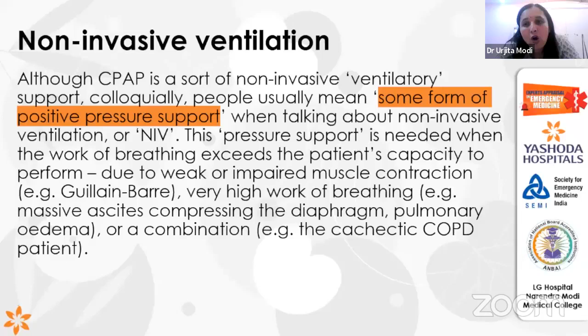And the machine has a trigger. The trigger point would be either an increase in the thoracic cavity volume or a decrease in the intrapleural pressure. This trigger will sense that the patient is starting inspiration. So at the start of inspiration, the machine will give IPAP with the help of pressure support. And then at the end of expiration, the machine will provide a certain flow. So the amount of pressure generated at the alveoli, which is almost equivalent to PEEP, is called EPAP.